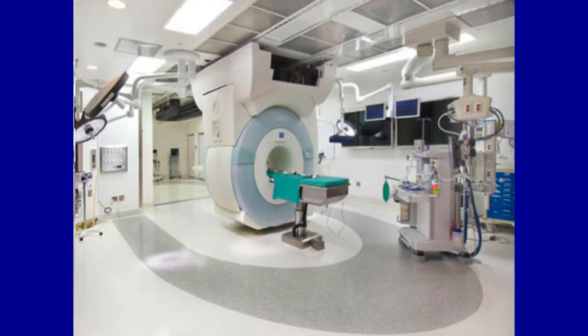So you come in, you would do the surgery here. You feel like you're done, the case is finished. Now you want to take a look with the intraoperative MRI to make sure you're finished. So then that door will open, and now you can see here's your standard 1.5 Tesla magnet that's on this track. Now it's going to start moving towards you. It's getting closer to the patient, and now the patient's head's in the gantry, and you're able to do your scan. Once the scan's done, then you just move the magnet back.